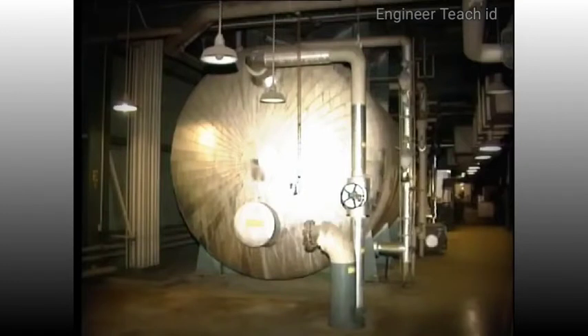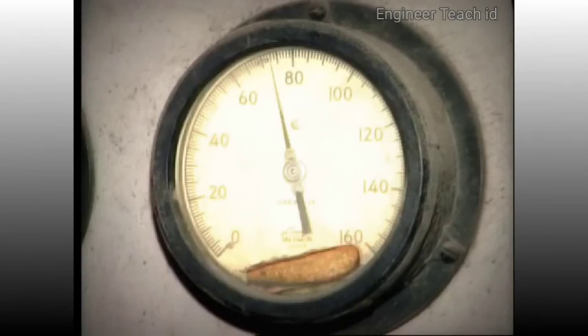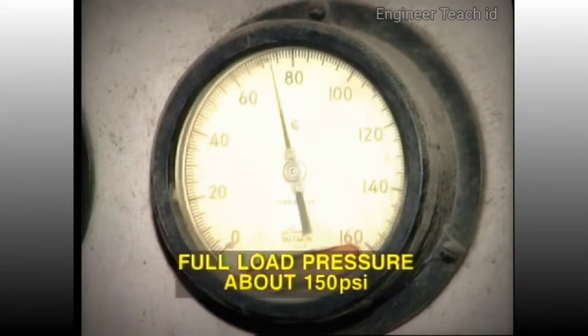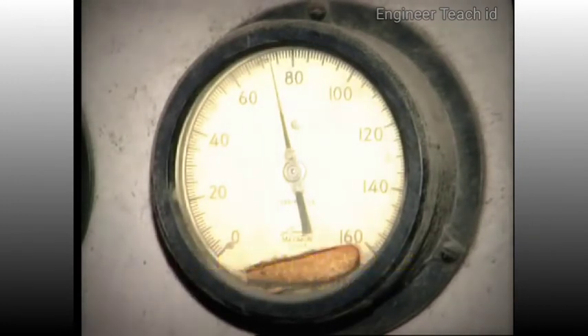This vessel is known as a de-aerator, as the mixing of steam and water liberates any dissolved gases, principally oxygen, from the water. We'll be talking more about the construction and function of feedwater heaters in the next segment. The pressure inside the de-aerator varies with the extraction steam pressure. At full load, this is likely to be, say, 150 psi. However, at lower load, this pressure would be considerably lower.